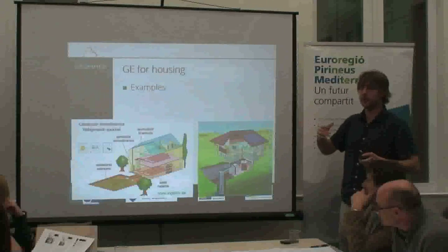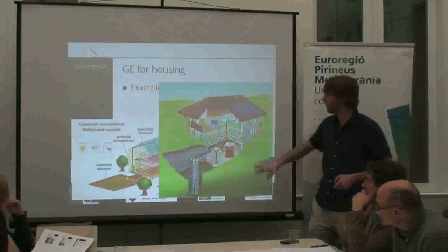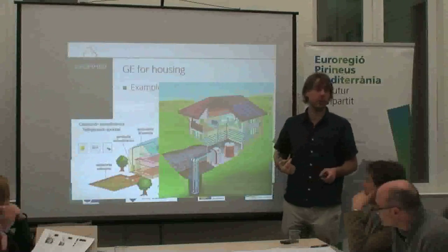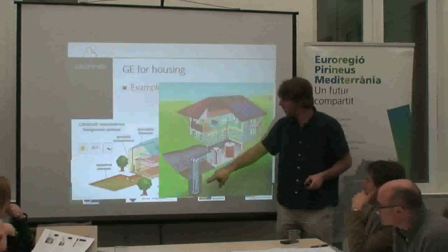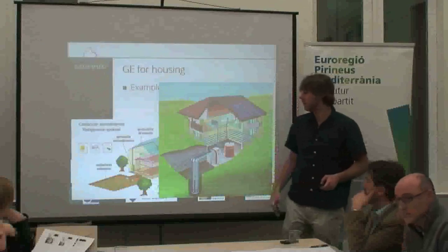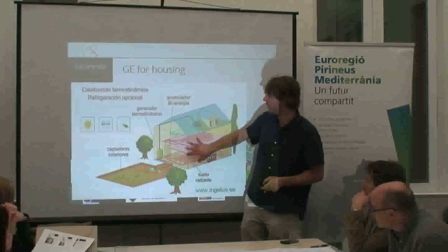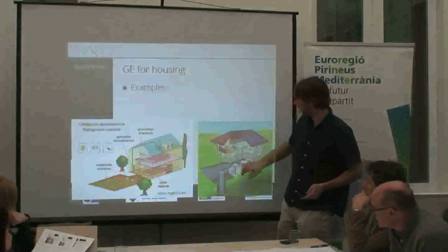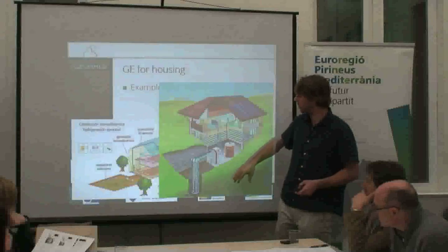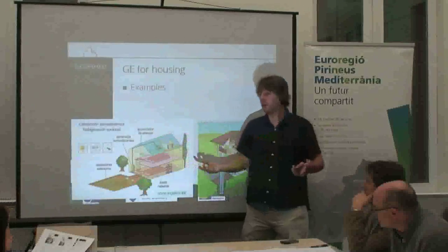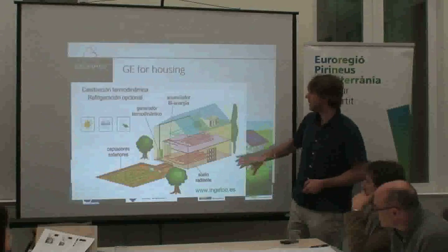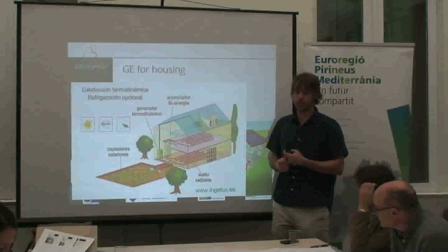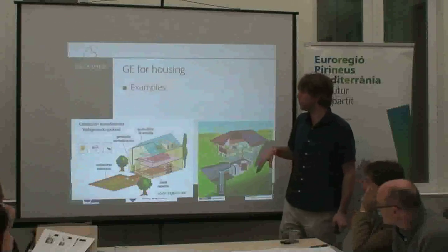They have to know which kind of geothermal energy you have. You have vertical geothermal, where you just drill and put a single U pipe. You put the pipes, and then you can exchange this energy with the underground using the vertical probe, or you can use the horizontal solution. That needs more surface, because of course you need more space. Here you have all this space underground, about 100 meters, and here we will have this kind of volume, but horizontally, so we will need more surface. These are mainly the two, or at least what we explain to the general public. We don't explain the open loop system, where we can also use water.